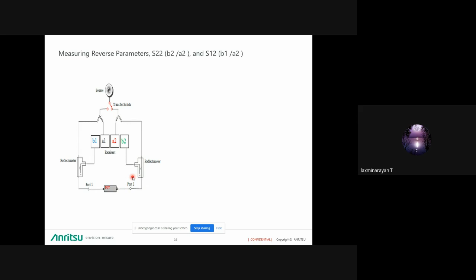Like this we measure S11 and S21. When you come to S22 and S12, the switch is shifted to port 2. From port 2 the signal goes to the A2 receiver, passes through the reflectometer and on to the DUT. In this case, A2 measures the incident energy on the DUT, B2 measures the reflected energy, and B1 measures the transmission energy.